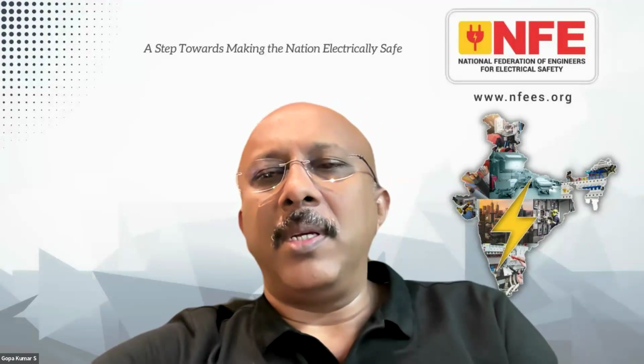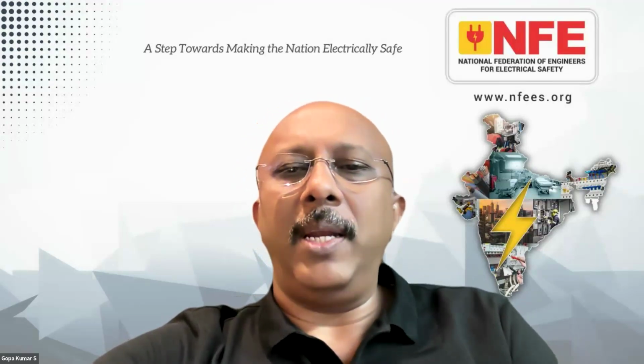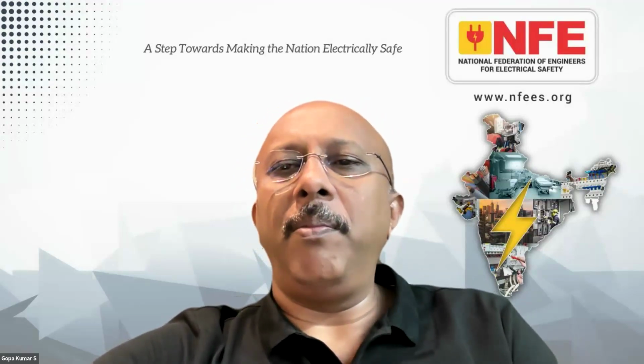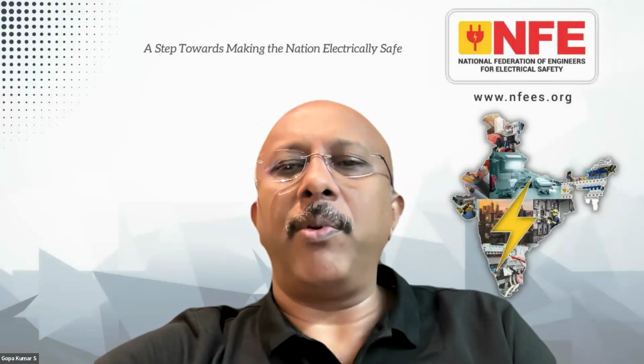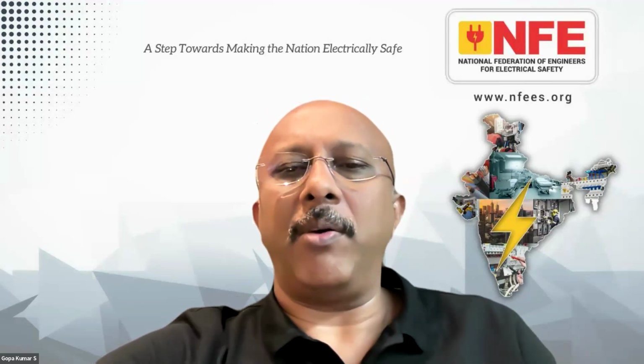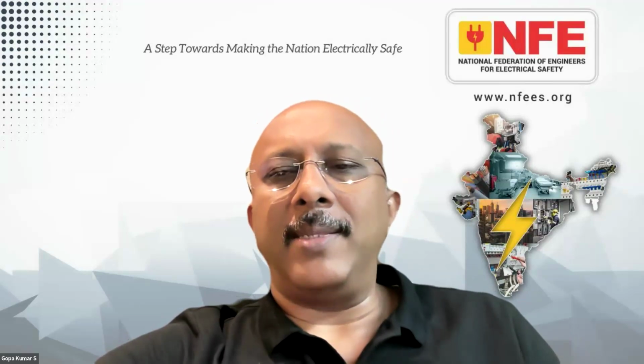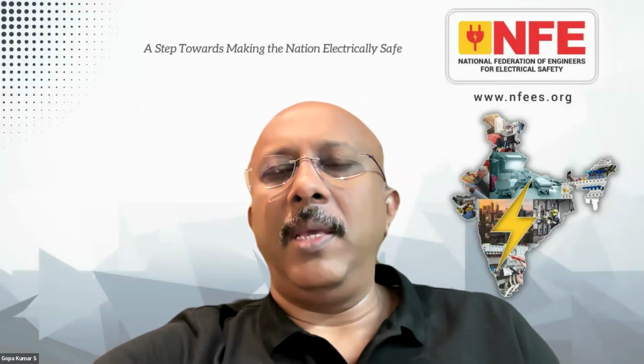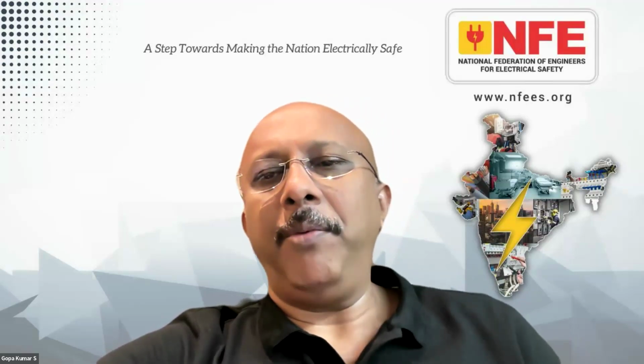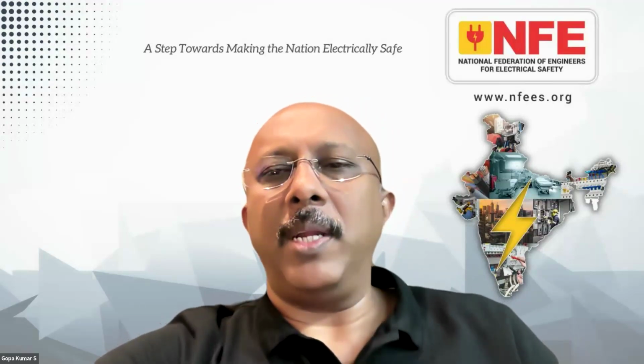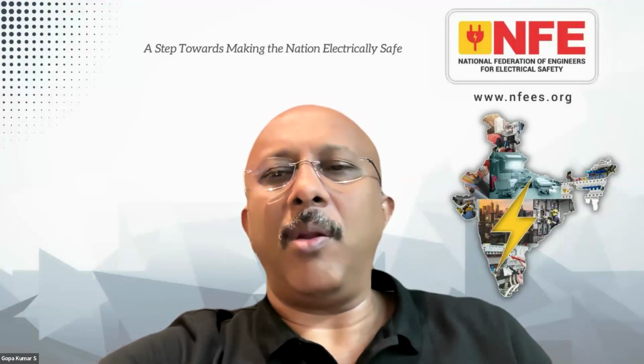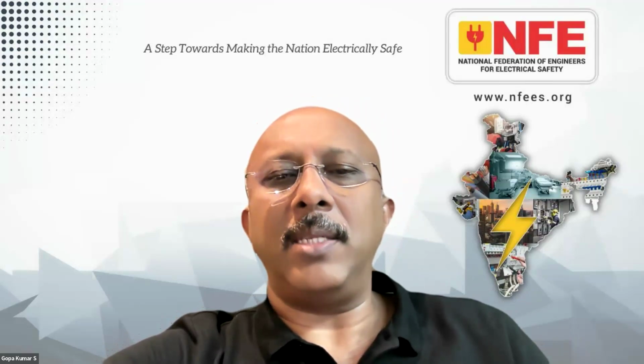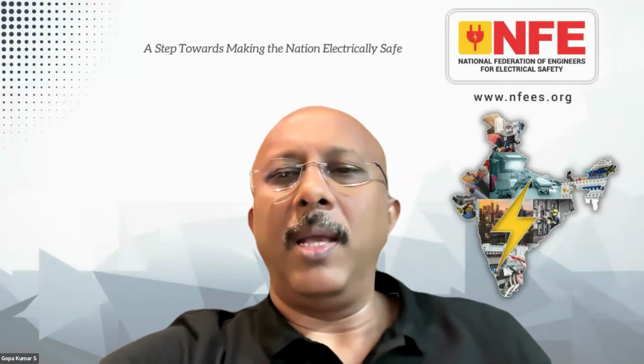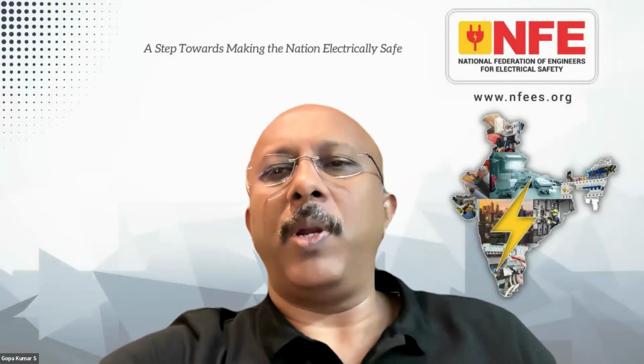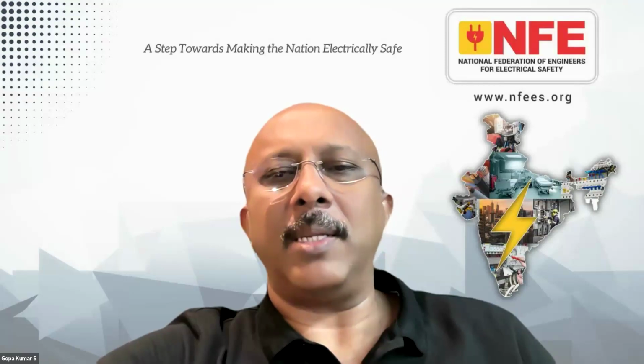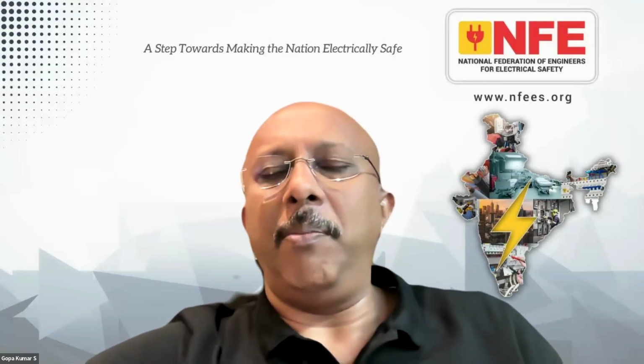But the problem is, selective reading is always a danger. If you want to implement safety in your building, you have to implement the complete requirement of the standard. For example, the basic protective measures, fault protective measures, protection against fire and thermal effect, and all these protective measures are not existing in most of our electrical installations. This is proved during our seminars and technical discussions with the participants.